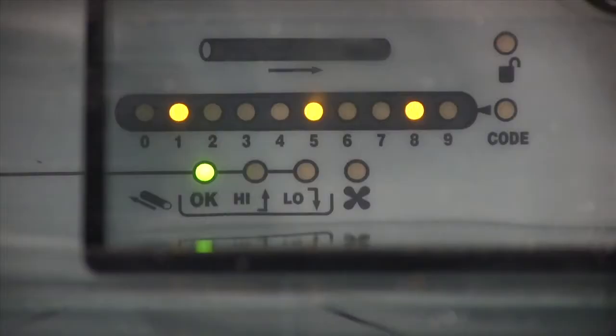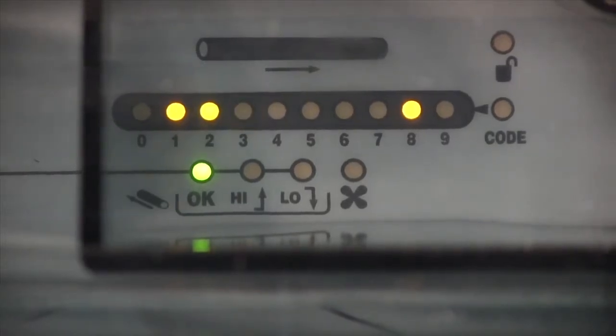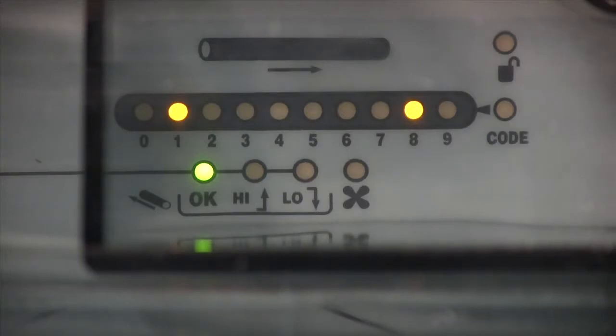This also means that the airflow through the unit may be supervised and a trouble signaled if it is out of calibrated ratings, something no traditional duct detector can do. The LEDs on the front of the unit indicate airflow levels. Let's watch what happens when I block the airflow going to the unit. You can see the LEDs are indicating reduced airflow. Eventually, the panel will go into trouble.